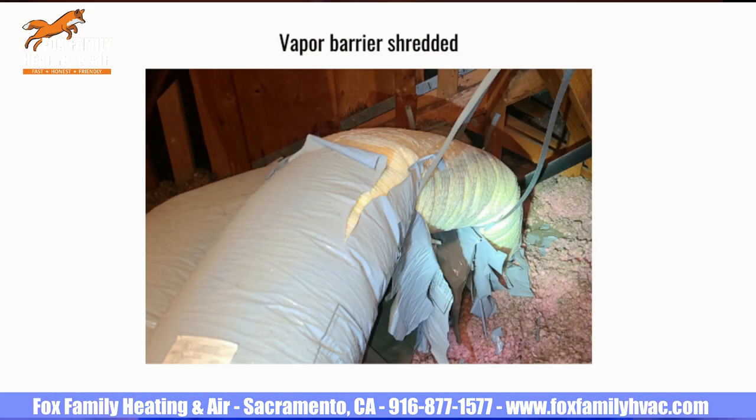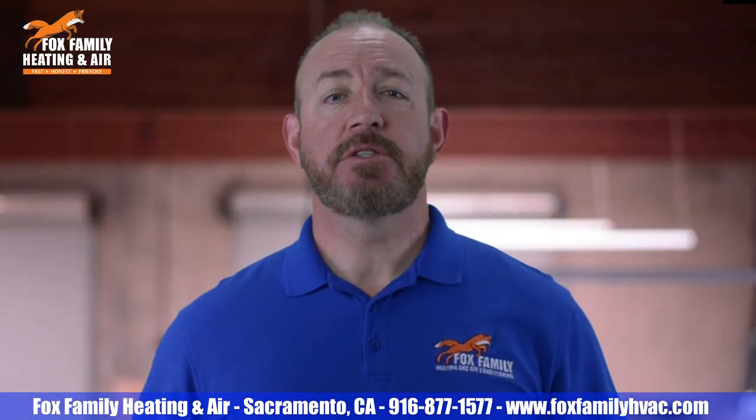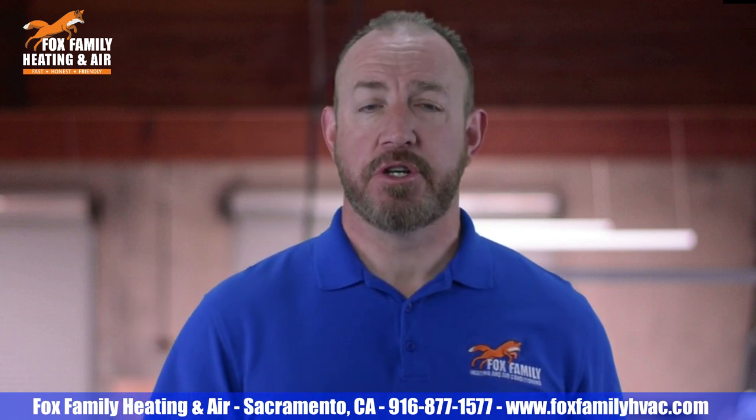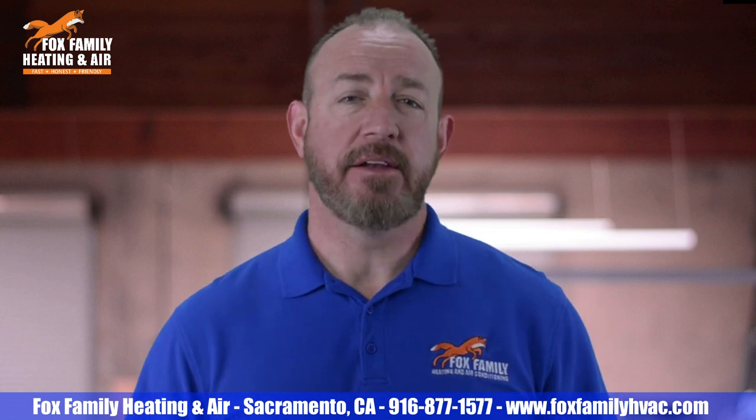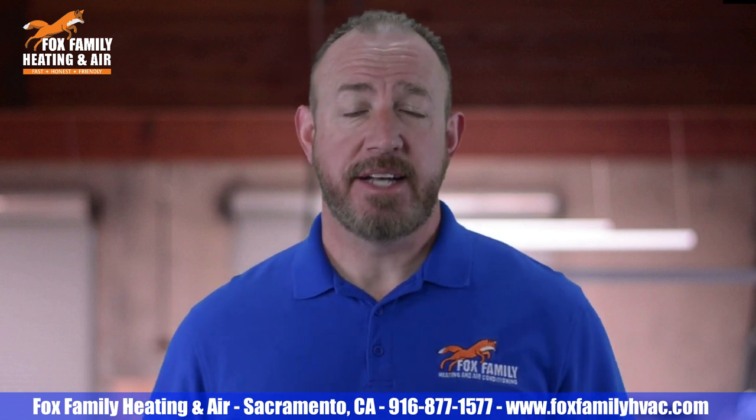The material on the outside of flexible ductwork is called the vapor barrier or vapor lining. It stops condensation from forming and dripping down onto the sheetrock or wood ceiling. After many years, vapor barriers will start to shred or fall apart due to heat and exposure to light from decorative attic windows. The same is true for insulation wrapped around the duct — if it's not covering the duct as it came from the manufacturer, heat from the attic will absorb into the conditioned air inside the duct, making the air warmer as it reaches the room. The difference between the temperature of the air going into the room and the temperature entering the return air grill in the hallway should be about 18 to 22 degrees.